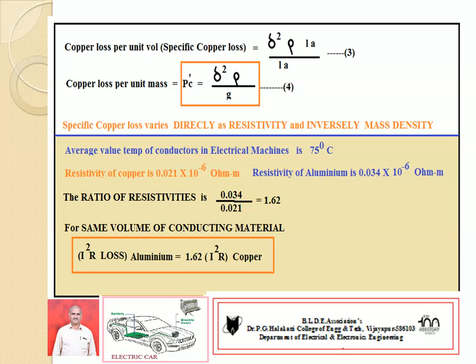Hence the rating of a machine is determined by the temperature rise. Therefore, the current rating of a machine using aluminium as a conductor is equal to 0.78 times that of a machine using copper as a conductor. Hence, by using aluminium as a conductor or winding, the output or current reduces by 22%. If you are using aluminium as the conductor, the rating reduces by 22%.